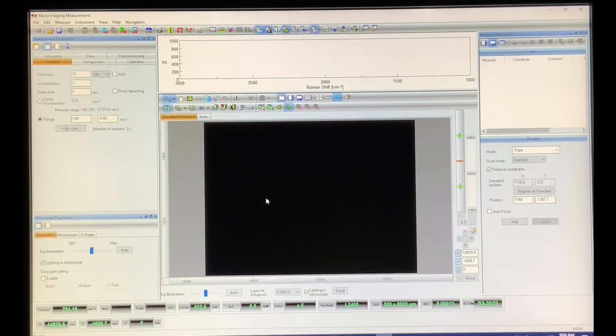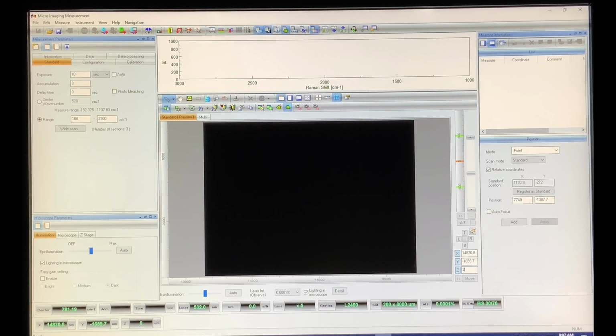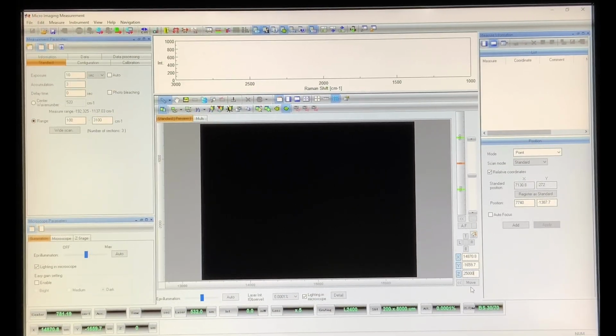So now that the software is loaded up, and we have our silicon calibration sample in the RAMAN, the next step is to move the stage up closer towards the lens and get the sample in focus. To move the stage up, there are two ways that I can do it, which is by using the scroll on the joystick, or by simply inputting the numbers into this Z coordinate here. So I'm going to start off by moving the stage to 25,000, and now I'm going to click move.